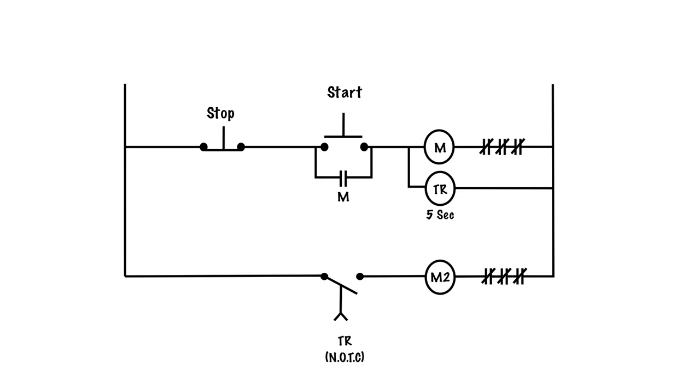Here we have a very simple circuit for sequencing. Let's say for some reason we don't want M coil and M2 coil to energize at the same time, meaning we don't want motor M to start at the same time M2 does. Perhaps there's too much inrush current. So we want M2 to start 5 seconds after M starts.